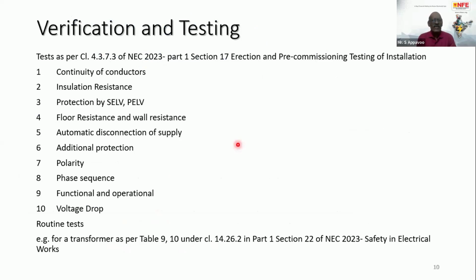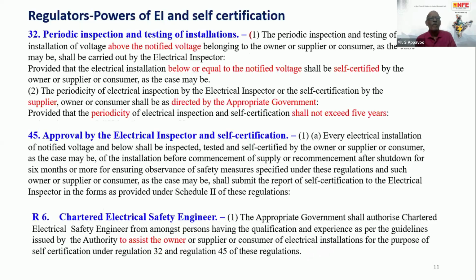After a complete installation, you have to go for verification and testing as per NEC 2023. It involves ten types of verification measures. Also, some routine tests are prescribed under Table 9 and 10 on clause 14.26.2 of Part 1, Section 22 of NEC 2023. So these are the provisions that have to be observed, the overall provisions. The intricate parts we are not going into. After providing these things, the regulators have to inspect.